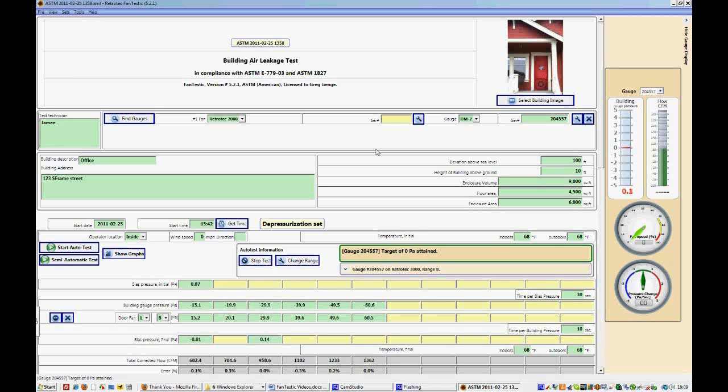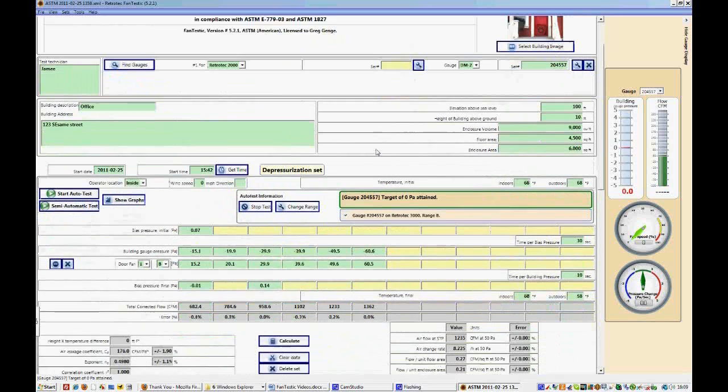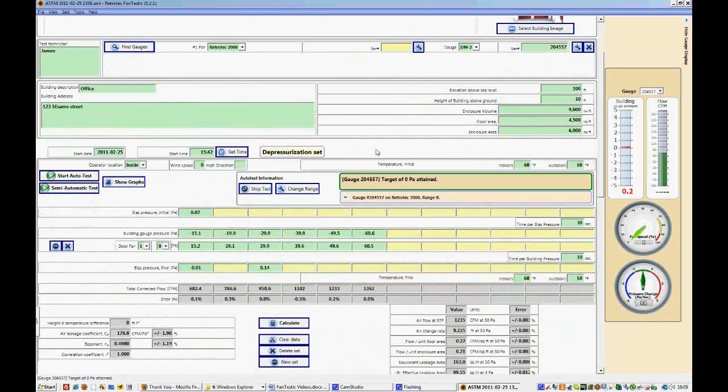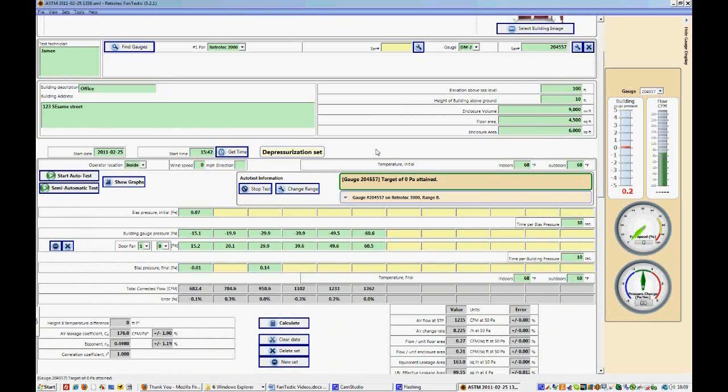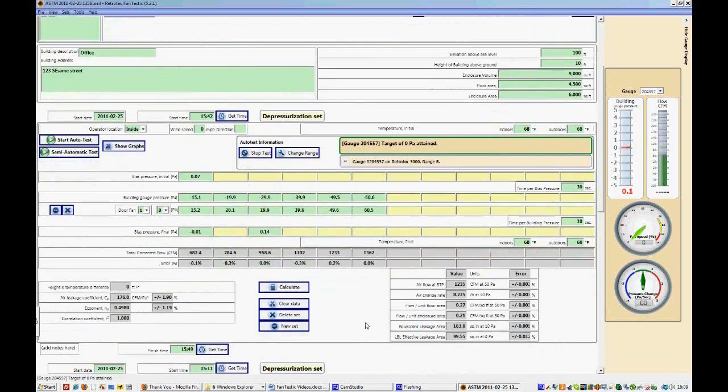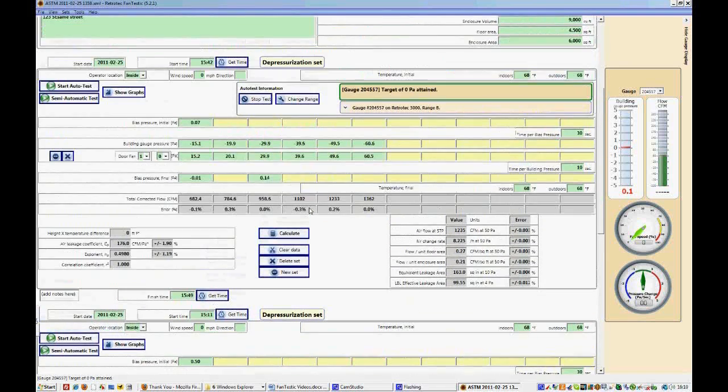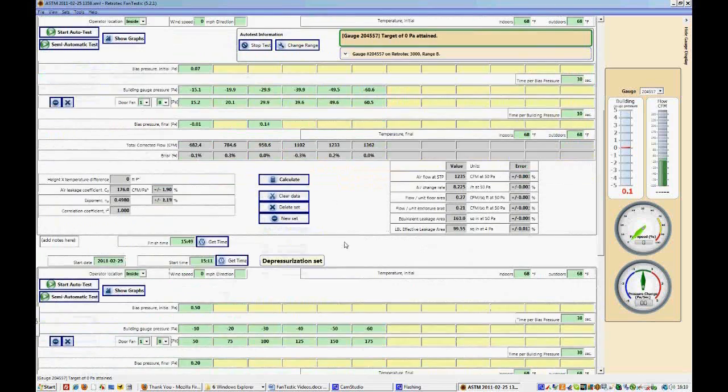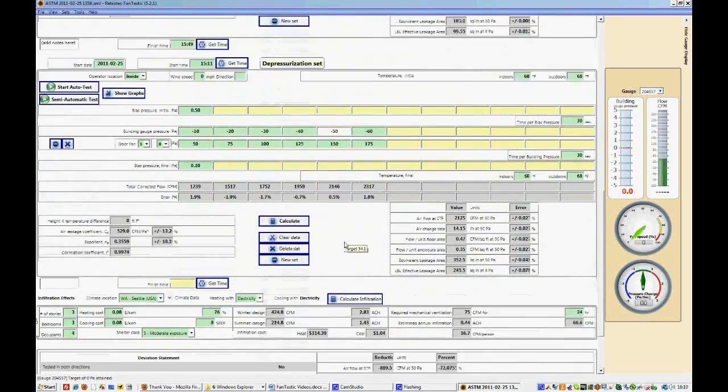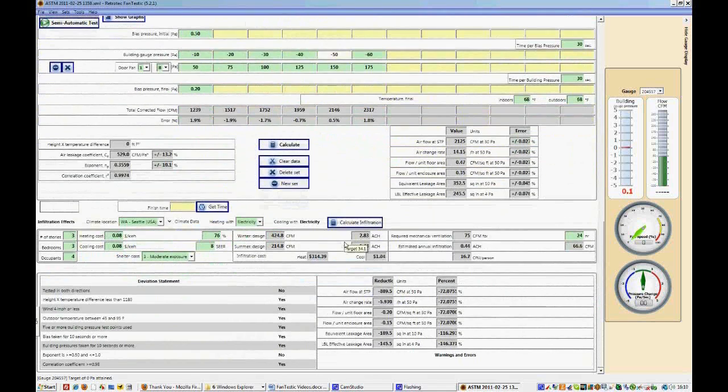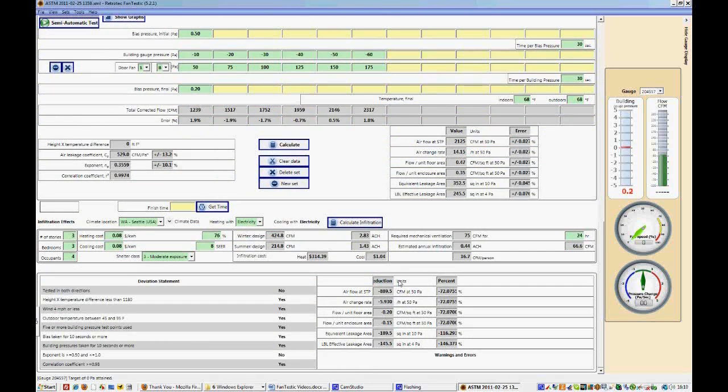One more thing that you can do with FanTestic is if you were at a client's house and you found some of the leakage areas, and you immediately wanted to change and fix some of the leak areas and find out how well that did with regards to air leakage. What you could do is run one test, select a new set, or run another test in the same direction. So right now we have two tests that were run in depressurization mode. And when we come down to the bottom here, we see that this says reduction. So FanTestic is assuming that you have completed one test, fixed the leaks, and completed a second test to determine how much better the air leakage is.